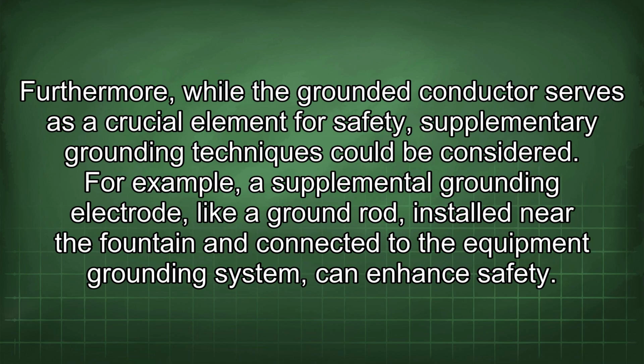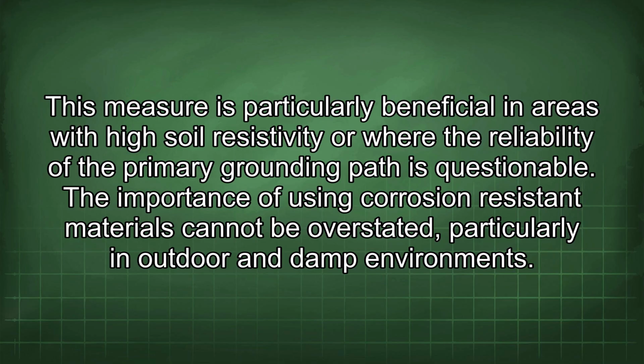Furthermore, while the grounded conductor serves as a crucial element for safety, supplementary grounding techniques could be considered. For example, a supplemental grounding electrode, like a ground rod, installed near the fountain and connected to the equipment grounding system, can enhance safety. This measure is particularly beneficial in areas with high soil resistivity or where the reliability of the primary grounding path is questionable.